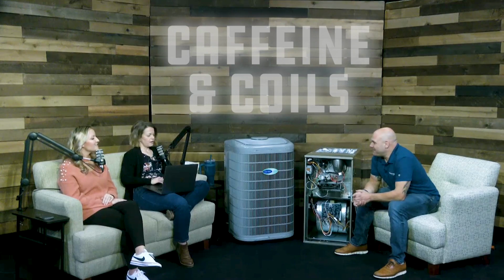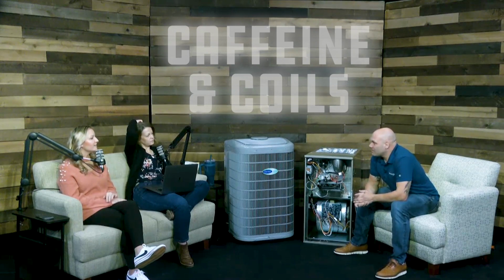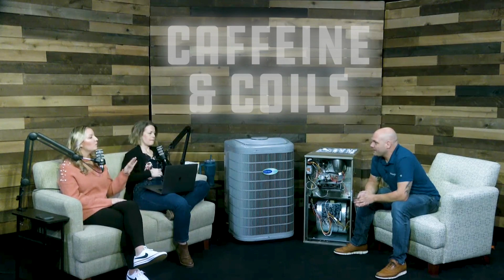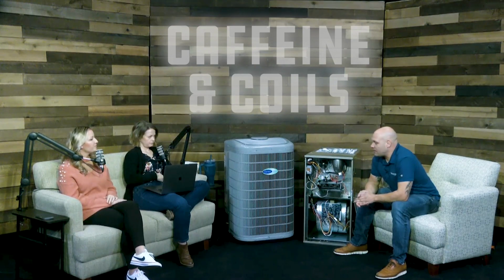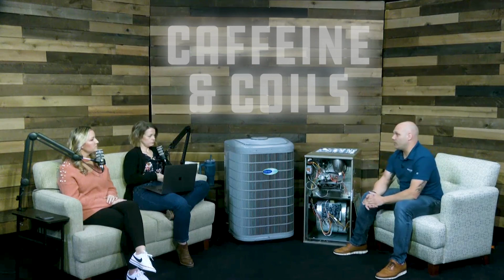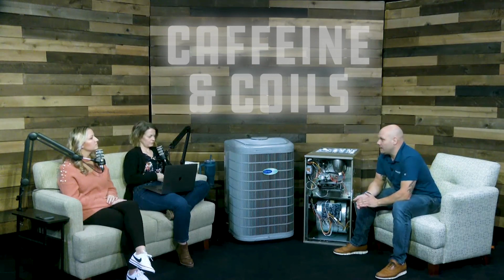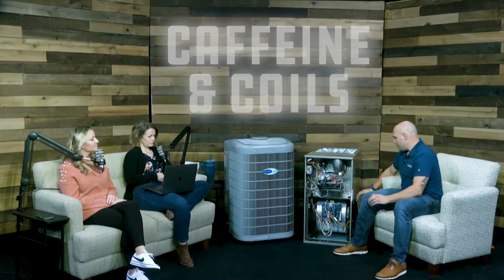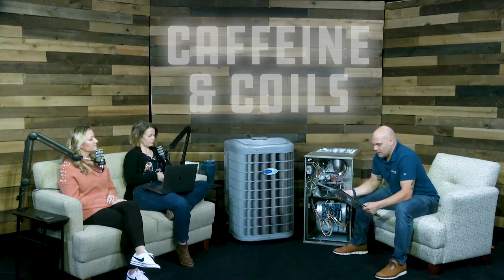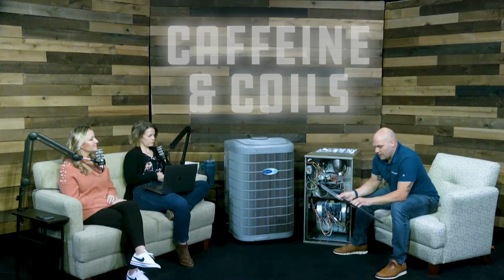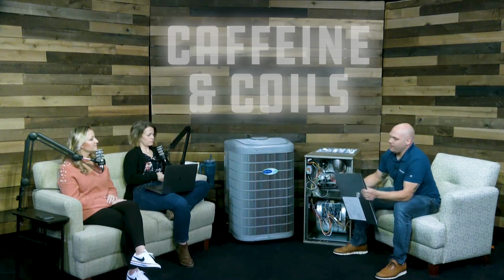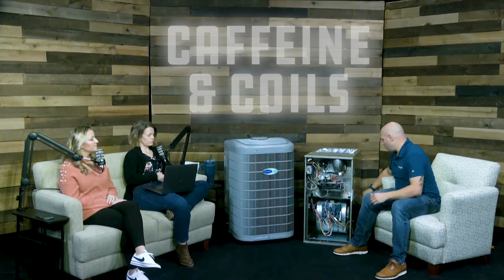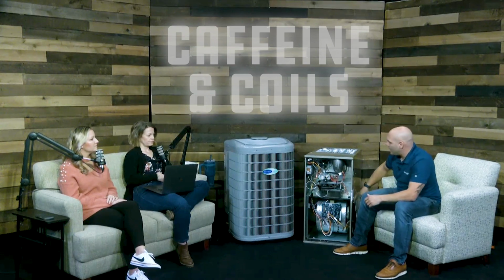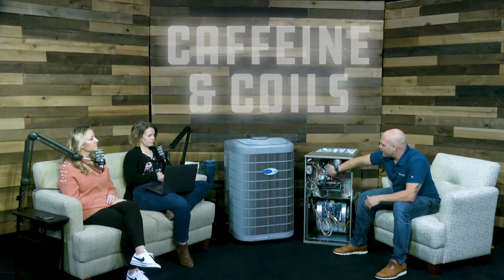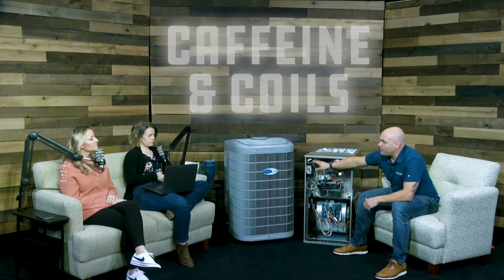Yeah, it was. So what are the most common issues you encounter in those 7 steps? What are the most common ones that you typically see fail? A very common error code that you would come across in the field is a code 33. I'm going to read it to you from the board. A code 33 is a switch has opened in the main limit circuit. But that could be a number of things. One of the first things that happen is the draft-induced motor has to spin, and then it has to activate this pressure switch. That could be a code 33, is the pressure switch.